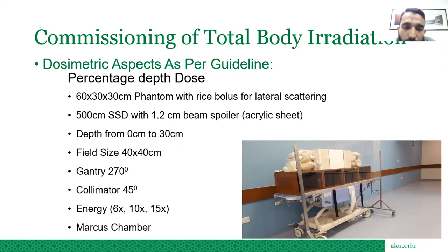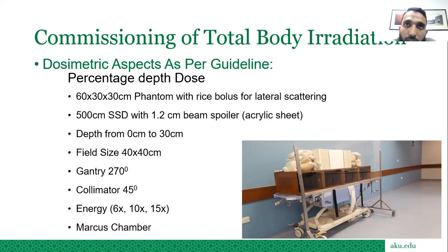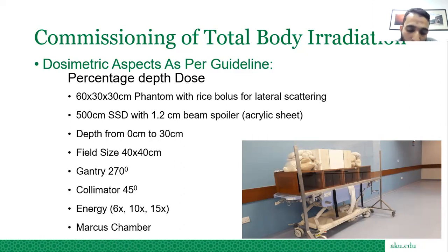We measured PDD for all three energies: 6X, 10X, and 15X. For matching PDD, we used a Marcus chamber for shallow depths because we need to measure surface and near-surface doses. That is why we use a parallel plate chamber or Marcus chamber.